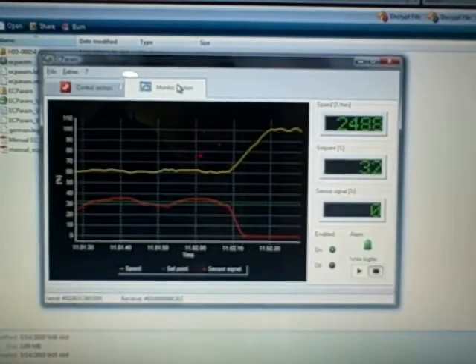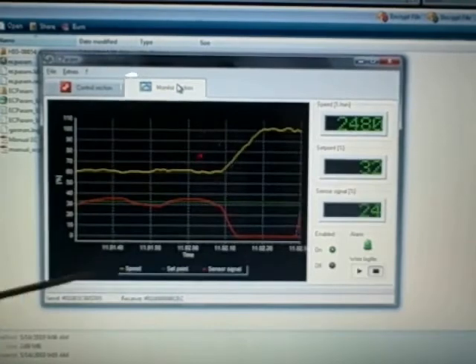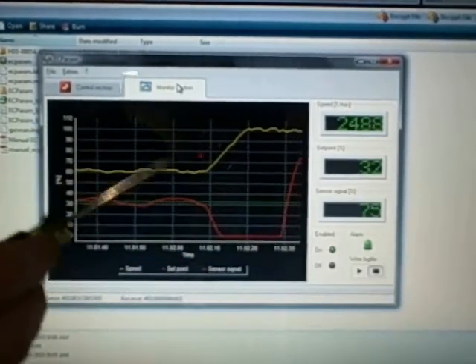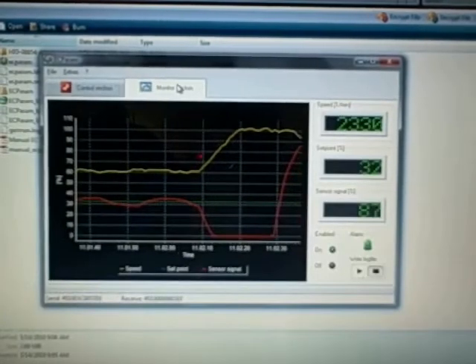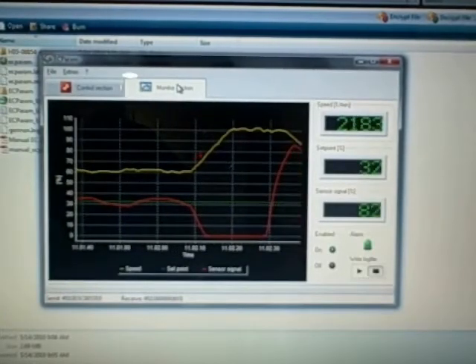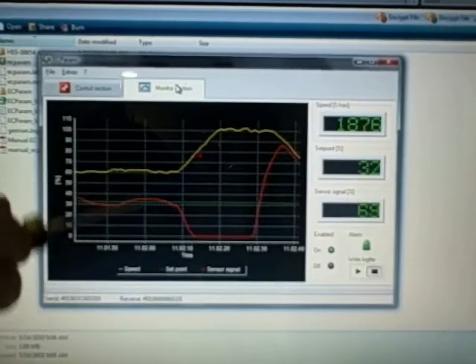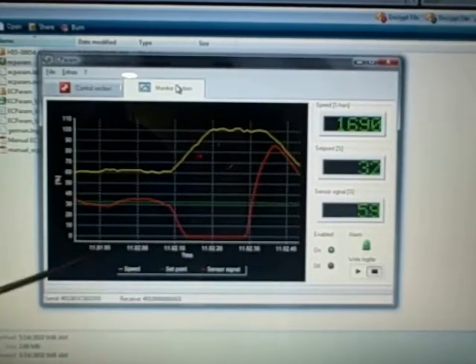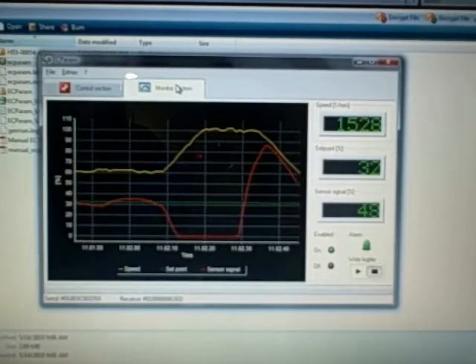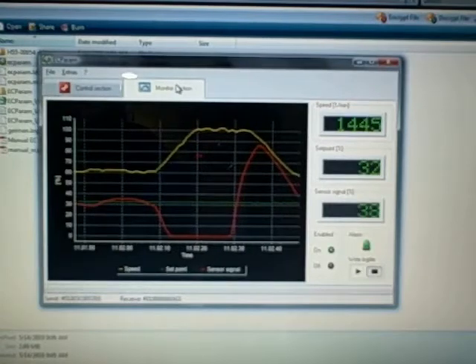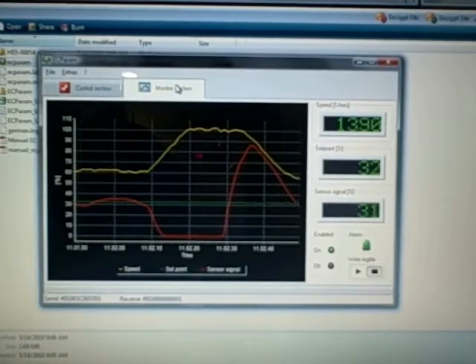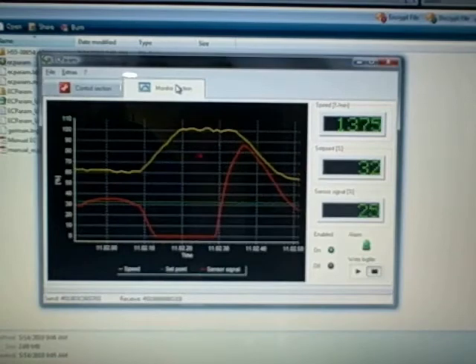And we'll open it back up. You'll notice the airflow difference here. And the fan will slowly start to ramp back down. You'll find something like this if your filters were completely clogged or your coil was dirty. And you'll notice here as everything starts to balance back out.